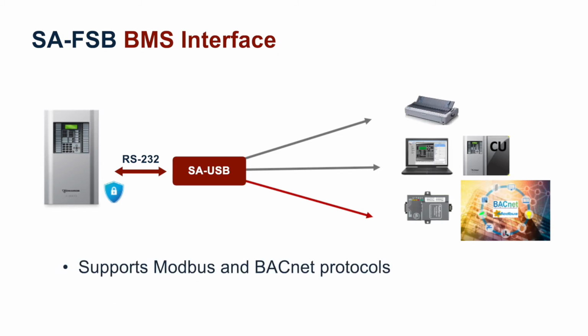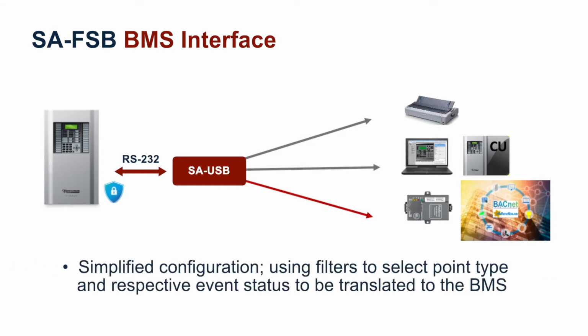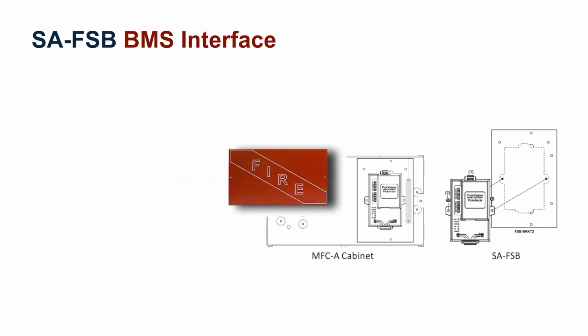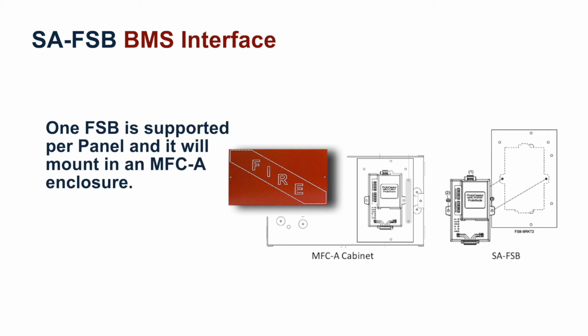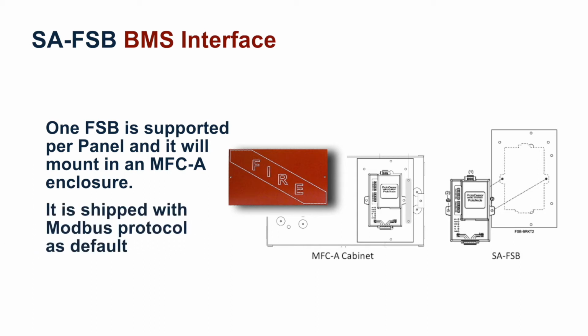Now the default configuration file stored with the FSB is under Modbus TCP protocol, but can easily be changed to BACnet. Now the configuration files and instructions to do so will be provided upon product release, of course. Now to simplify the configuration process, filters are included to allow the user to select what points with their respective event status are to be translated and sent to the building management system. Now keep in mind, with the Field Server Bridge, one Field Server Bridge is supported per panel, and it will mount in an MFC-A enclosure as shown. I did mention it is shipped with the Modbus protocol as default.